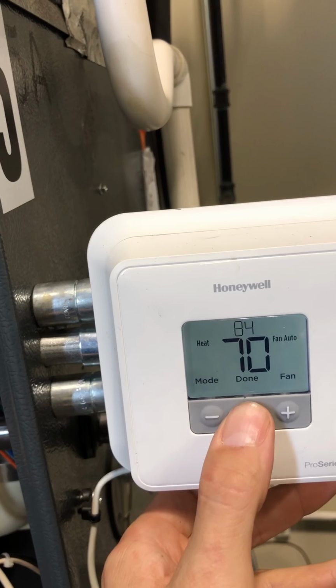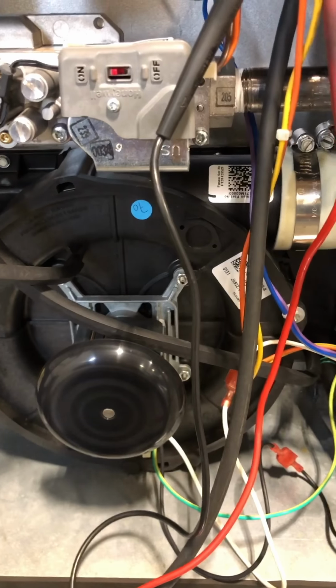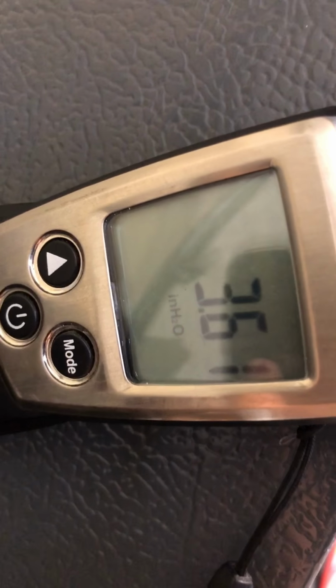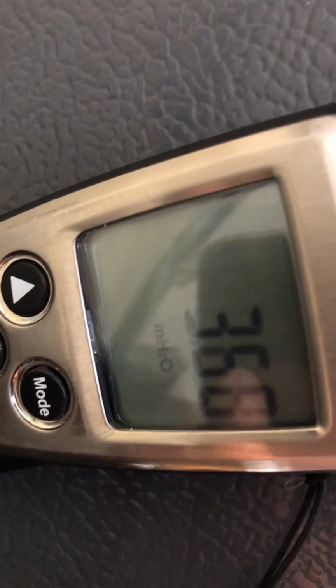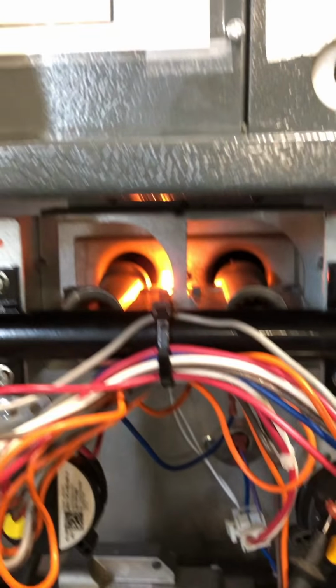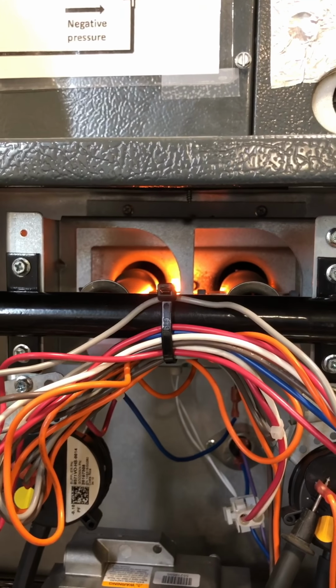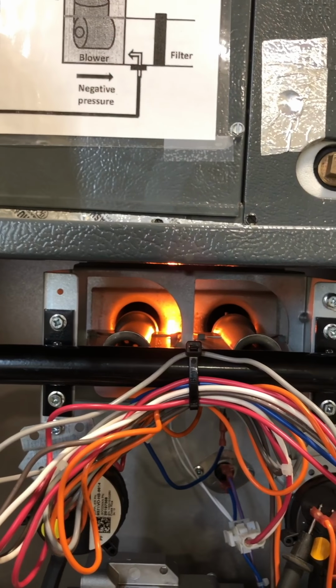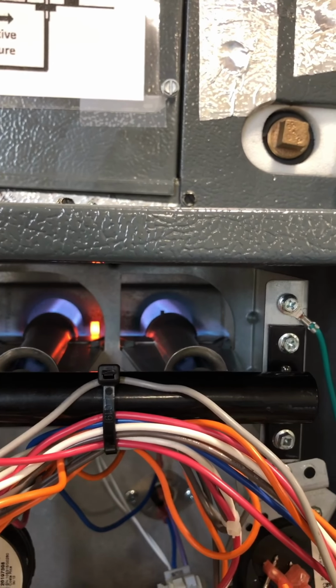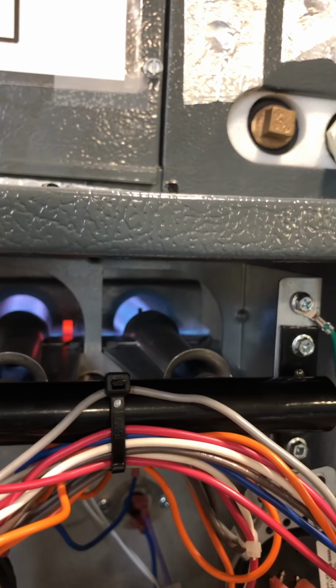Come on. Inducer started up. We've verified this was open. The inducer started. It's now closed. My probes aren't in there very tight, so we have a little bit of voltage there, but I am now pulling a proper vacuum, way over what I need, which is just fine, but I have at least 1.1 inches of water column on my negative probe. There goes our hot surface ignition. Gas valve, flame. After a few seconds, we're sensing that there's a flame with our flame sensor.